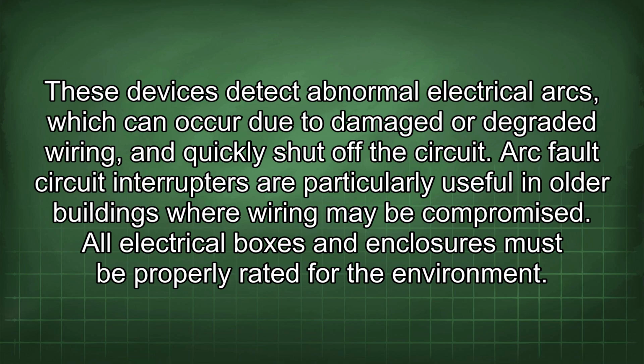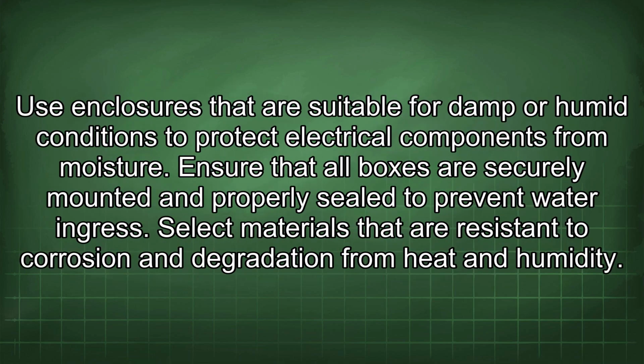All electrical boxes and enclosures must be properly rated for the environment. Use enclosures that are suitable for damp or humid conditions to protect electrical components from moisture. Ensure that all boxes are securely mounted and properly sealed to prevent water ingress. Select materials that are resistant to corrosion and degradation from heat and humidity.